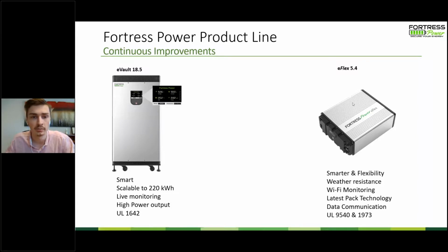Brian, is there a three-phase solution on grid and off grid, 208 480? So the Sol-Ark converter can do three-phase. If it's 208 480, I'd have to honestly find out for you. I believe it is, but I could be wrong. Don't quote me on that. But you could use the Sol-Ark in that kind of application. You would just have one inverter per phase, so you'd put three of them. Usually this is for larger residential, maybe some smaller commercial, but it's certainly a possibility.